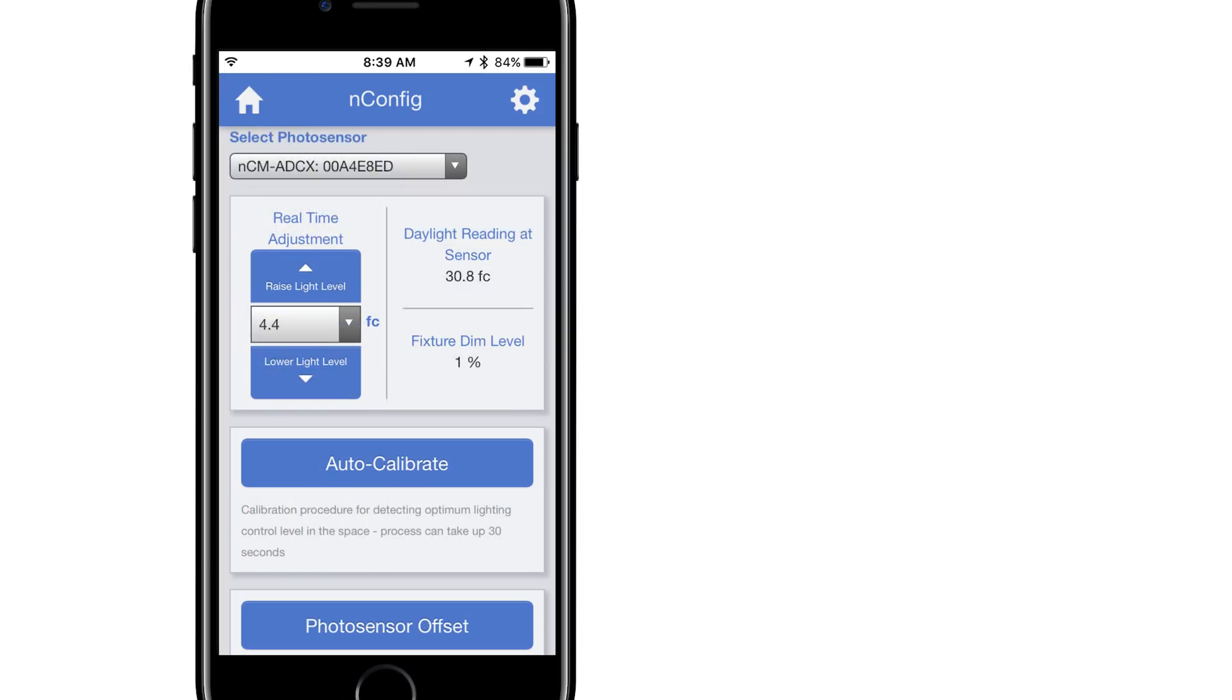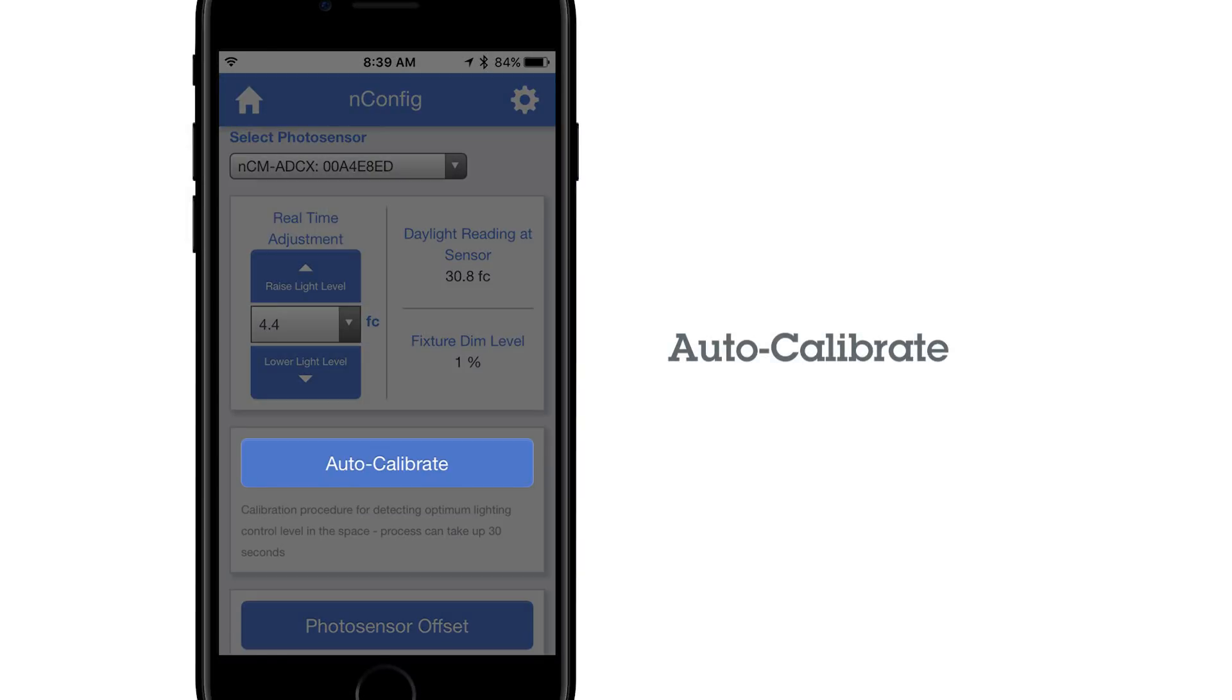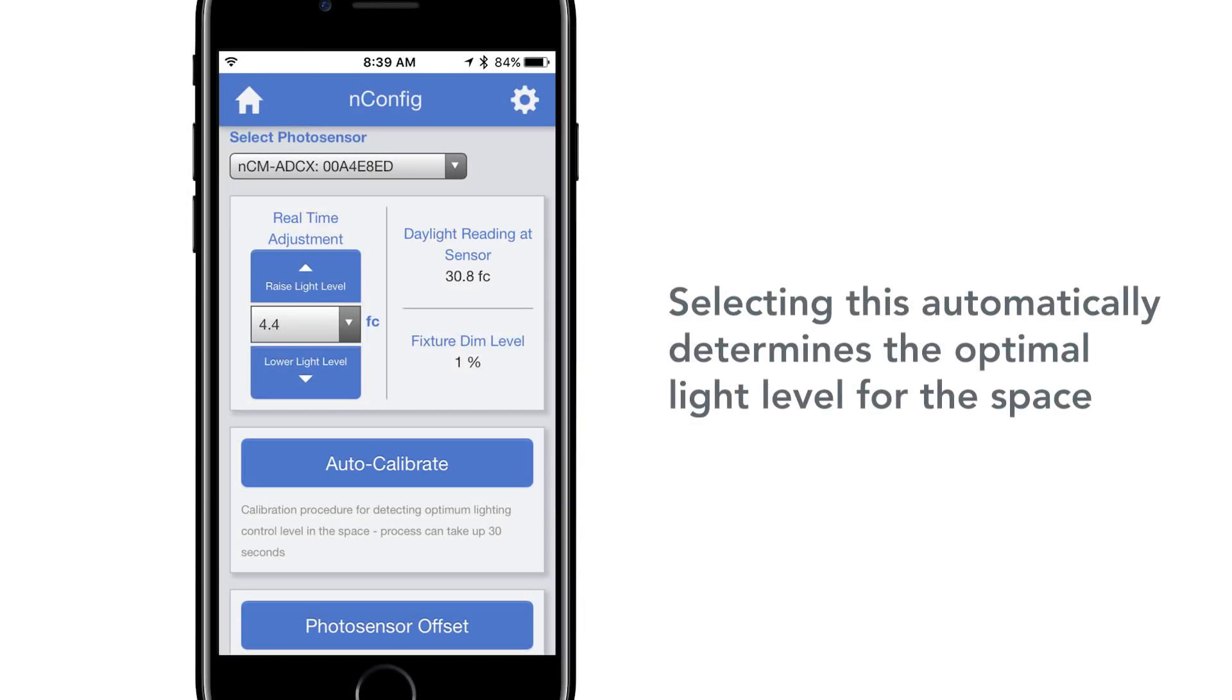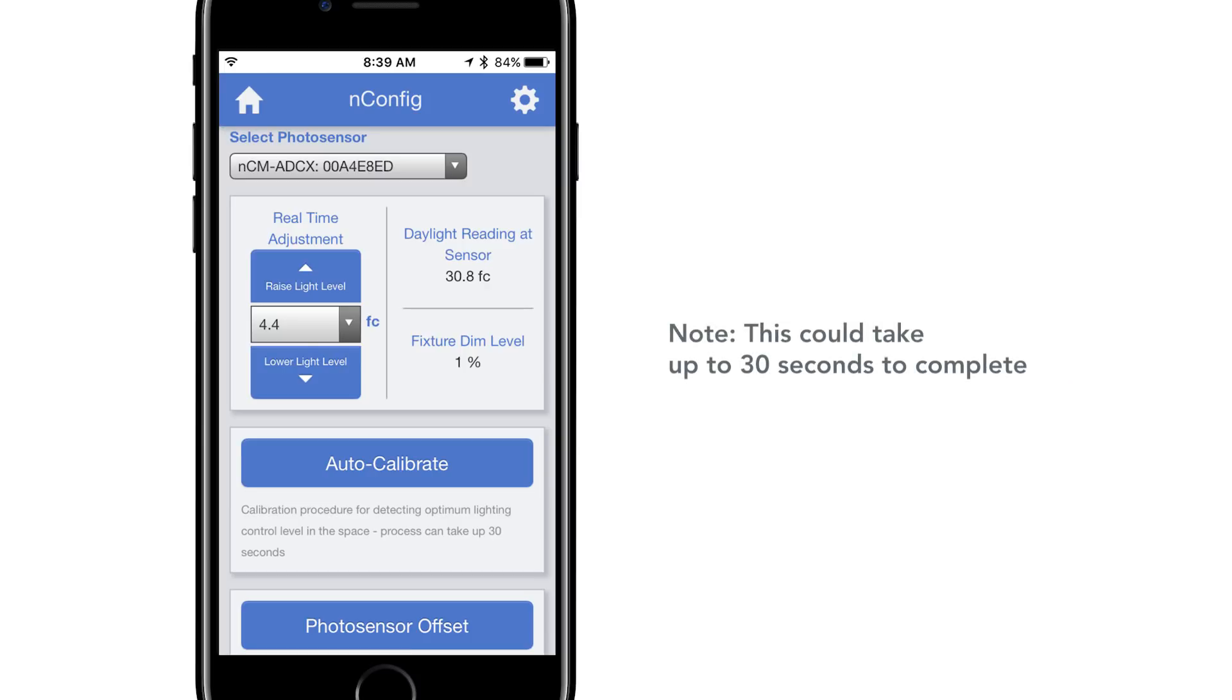If you are calibrating a sensor for the first time, auto-calibrate. Selecting this feature runs the sensor through an auto-calibration, which turns the lights off and on a series of times to determine the optimal light level for the space. Please note this could take up to 30 seconds to complete, and all app features will lock out during this time. Lights will turn off and on up to 4 times during the calibration.